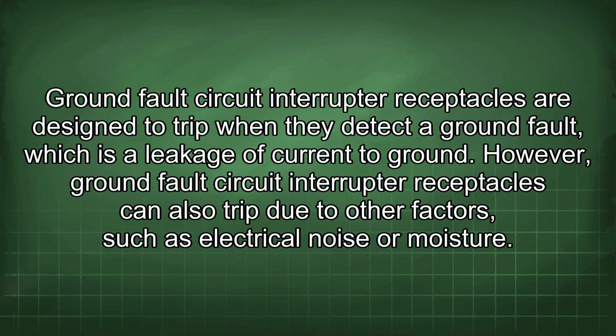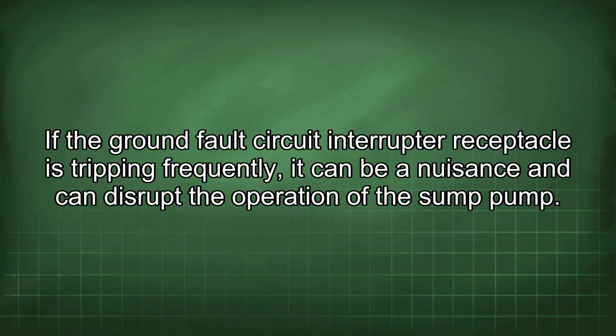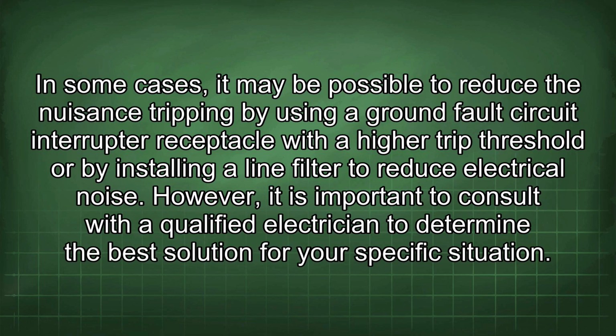Ground fault circuit interrupter receptacles are designed to trip when they detect a ground fault, which is a leakage of current to ground. However, ground fault circuit interrupter receptacles can also trip due to other factors, such as electrical noise or moisture. If the ground fault circuit interrupter receptacle is tripping frequently, it can be a nuisance and can disrupt the operation of the sump pump. In some cases, it may be possible to reduce the nuisance tripping by using a ground fault circuit interrupter receptacle with a high trip threshold or by installing a line filter to reduce electrical noise. However, it is important to consult with a qualified electrician to determine the best solution for your specific situation.